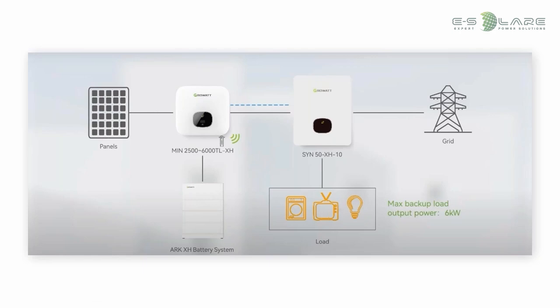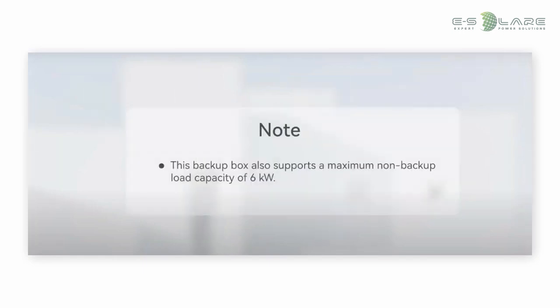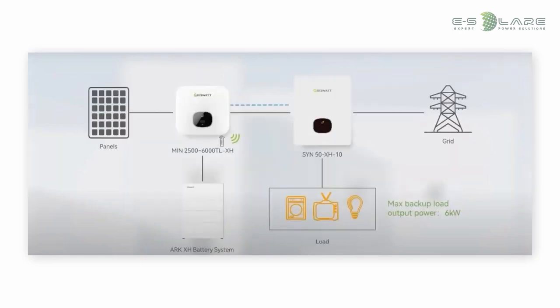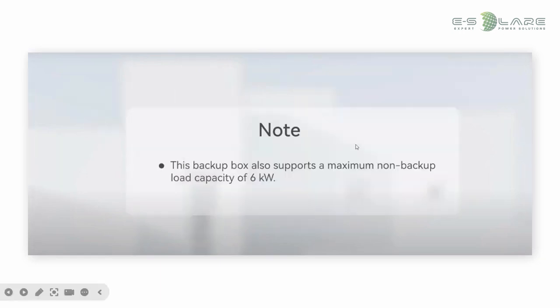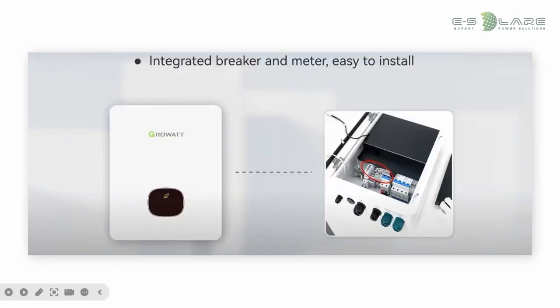And one thing you need to notice is the maximum backup load is 6 kilowatt, but this number is reduced by the inverter. So if you install a 2.5 kilowatt inverter, the backup is 2.5 kilowatt. If you want to achieve 6 kilowatt, you need to choose a 6 kilowatt inverter. And also this SYN supports a maximum non-backup load capacity of 6 kilowatt. And inside of this device, you can see there's a single phase meter and a breaker.